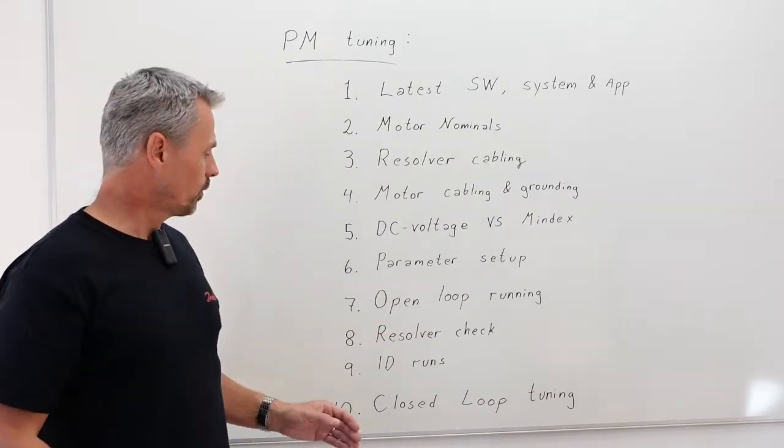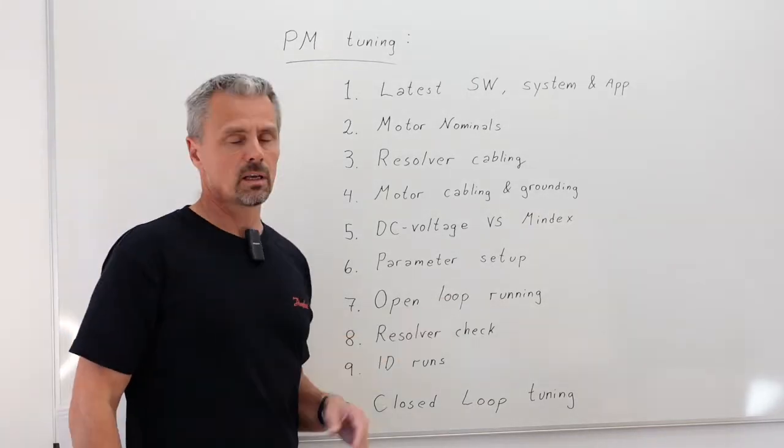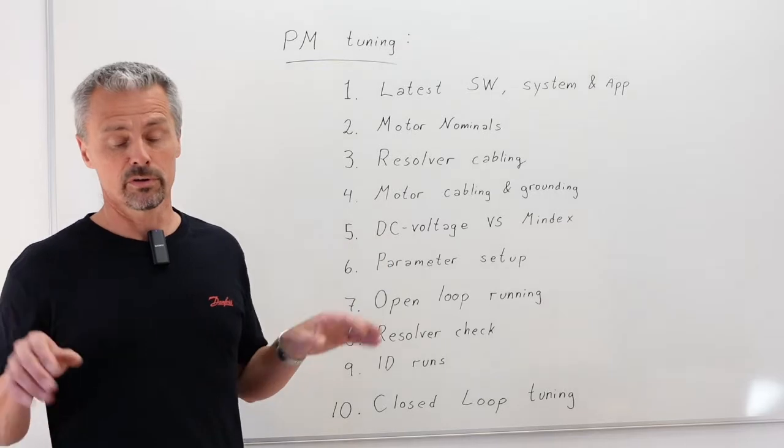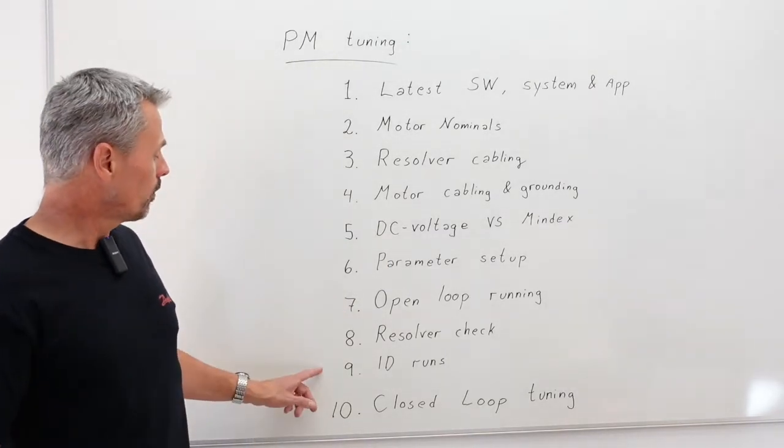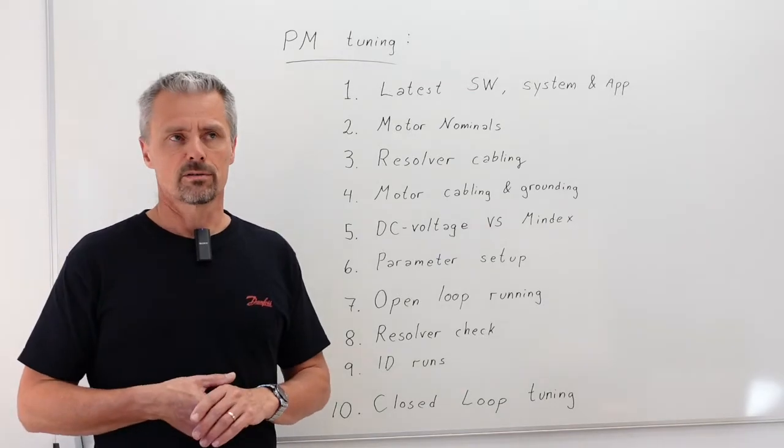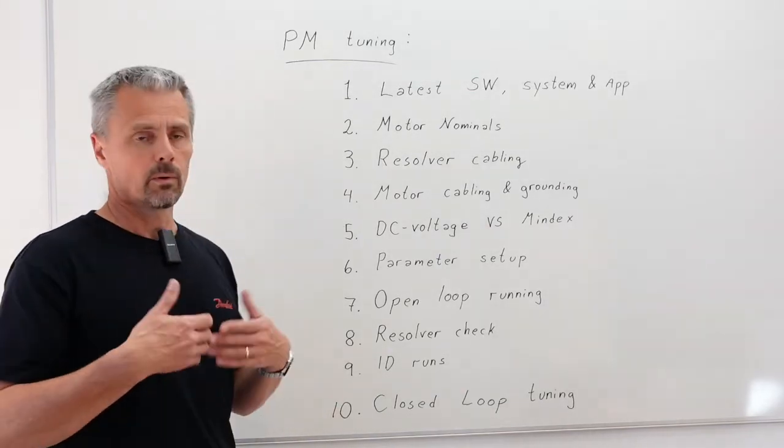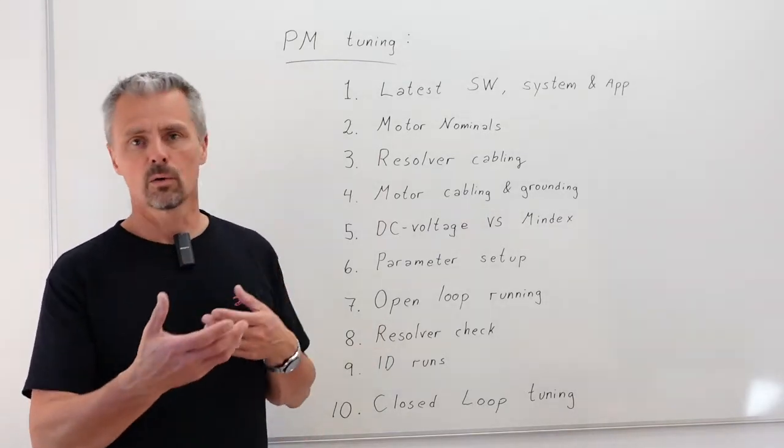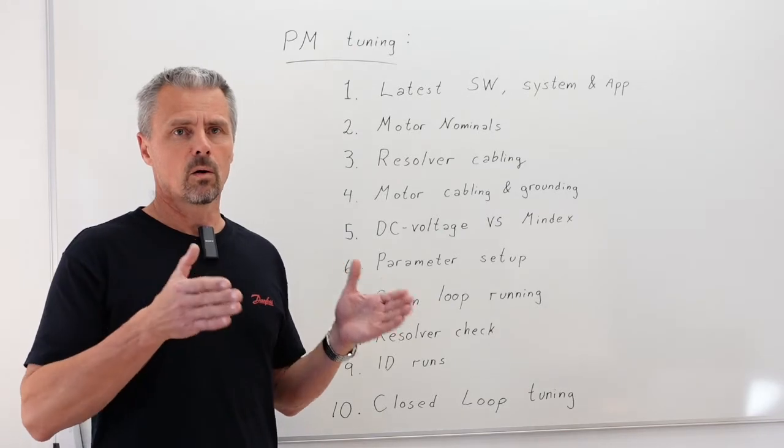When we run in the open loop we will check the integrity of the resolver signal - direction, noise, scaling and so on. Then we come to the identification runs. And that is several runs. It will be without rotation, with rotation, encoder run, and then at last we will run ident all.